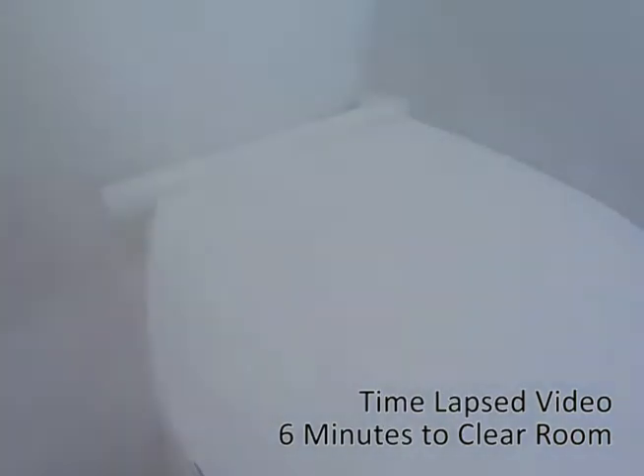After 6 additional minutes of running the fan without injecting additional smoke, the test was suspended. A small amount of residual smoke was still visible in the chamber at the time testing was stopped. The residual smoke was primarily along the floor of the test chamber and did not appear to be dispersing.